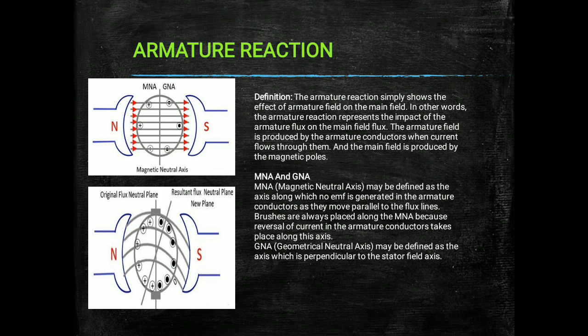The next part is MNA. MNA stands for Magnetic Neutral Axis. It may be defined as the axis along which no EMF is generated in the armature conductor, as they move parallel to the flux lines — that means in that axis no EMF is induced. GNA stands for Geometrical Neutral Axis, defined as the axis which is perpendicular to the stator field axis. In ideal conditions the GNA and MNA coincide with each other, but due to armature reaction the MNA shifts from the GNA by an angle theta.